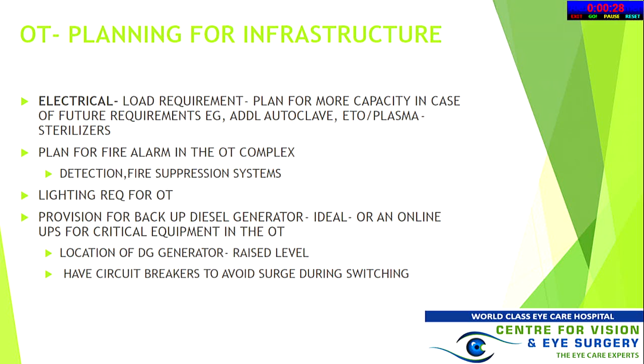When planning the infrastructure, a very important part is electrical load planning. Plan for a capacity that covers future requirements - additional autoclave, ETO, plasmas. Plan for a fire alarm. Lighting is also required for the operation theatre. Provision for a backup generator is ideal, and if you have very critical equipment, you need an online UPS. The generator location should preferably be on a raised level in case of floods, and have circuit breakers to avoid surge, because we burnt our hands on this about three years back.